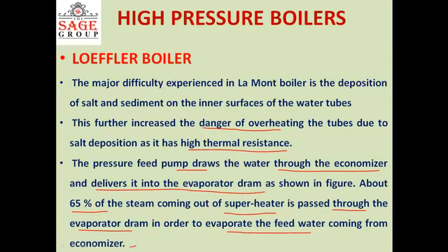So here the principle is different, because in this boiler we use the principle of the open or direct contact heat exchanger, in which two fluids are mixed together. So water as well as the steam coming from the superheater are mixed together, and the heat is transferred by the steam to the water to evaporate it. That will definitely eliminate the formation of salt on the inside surface. So this is the advantage.